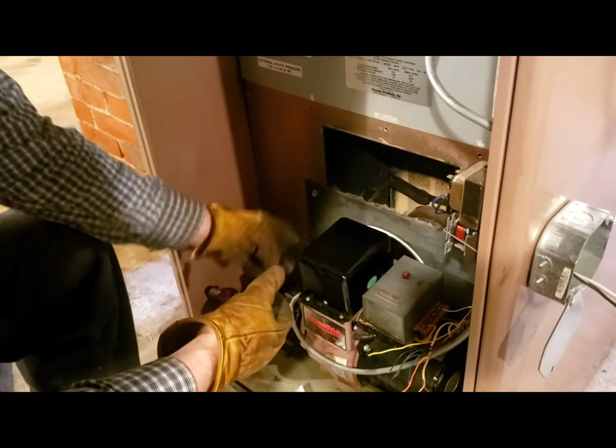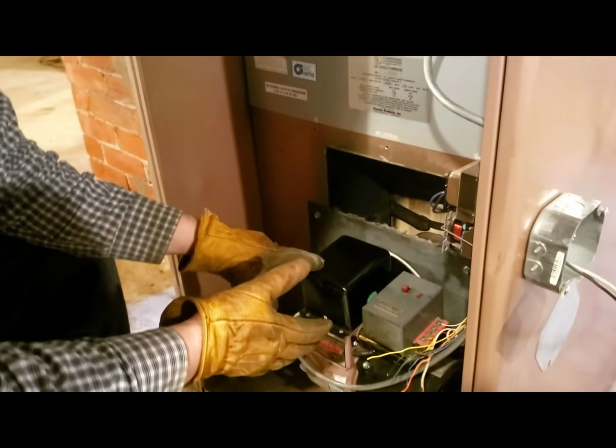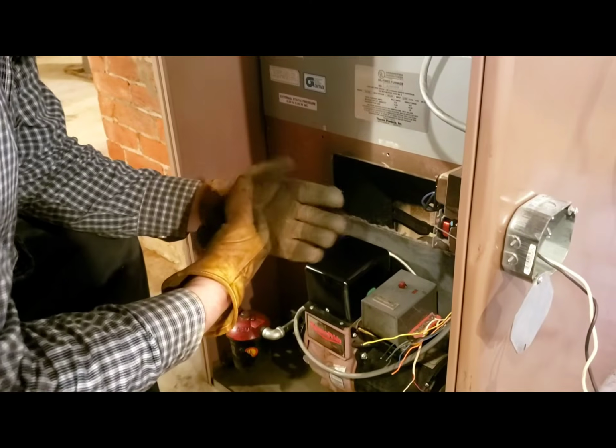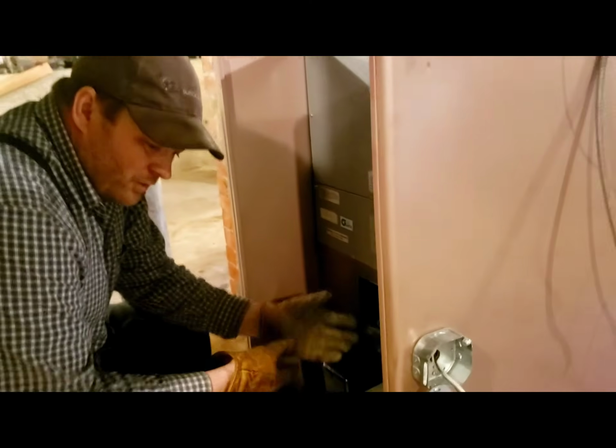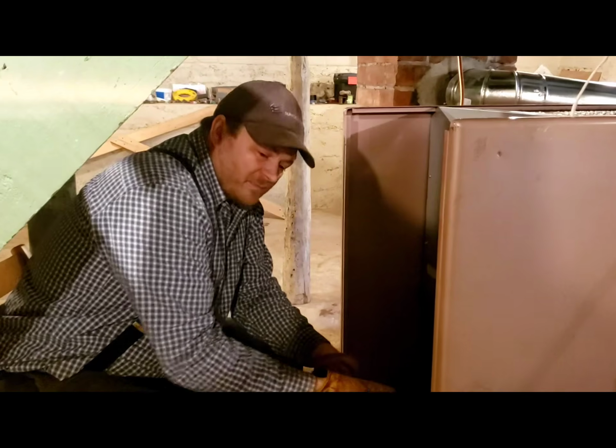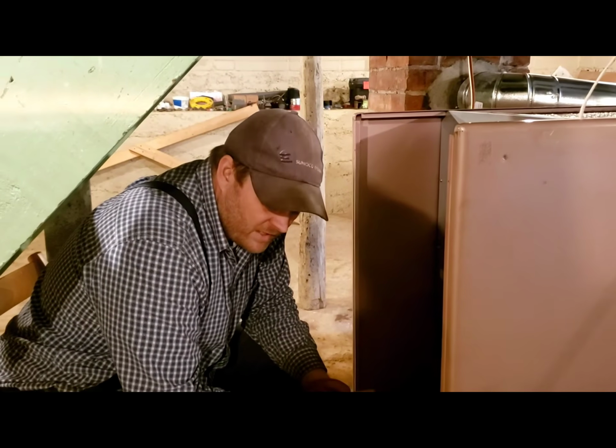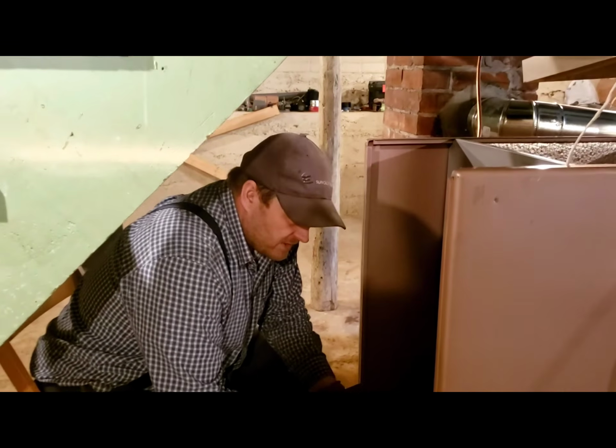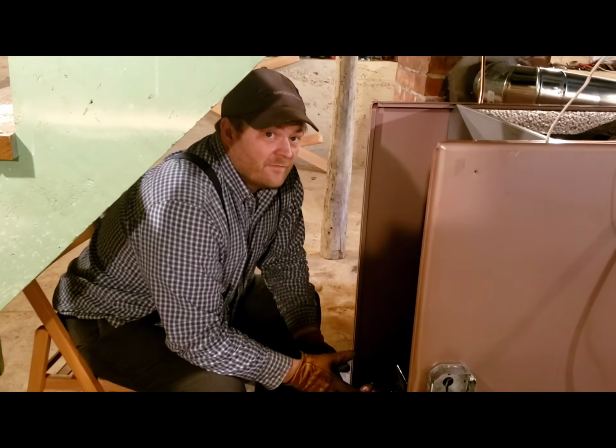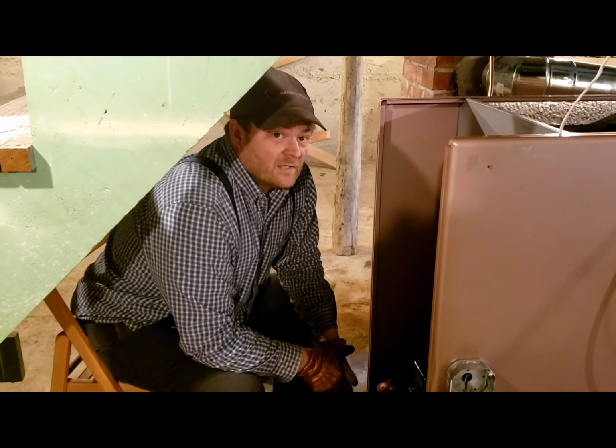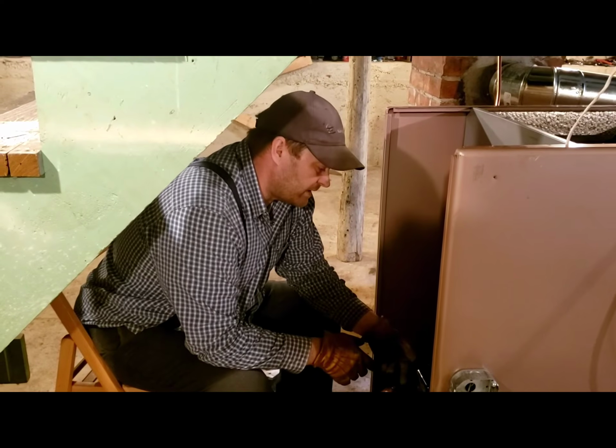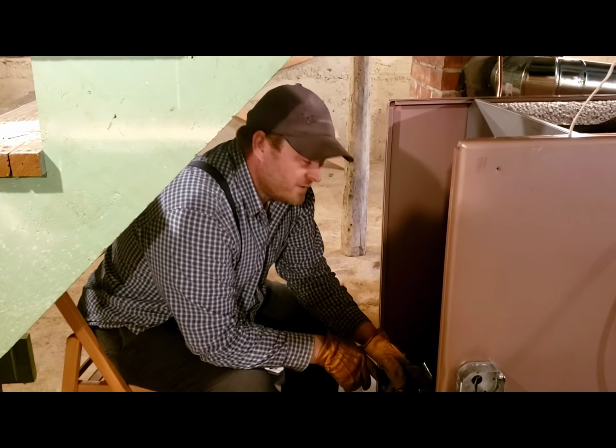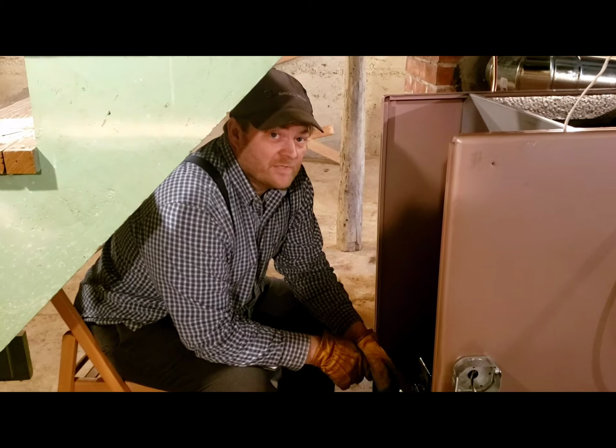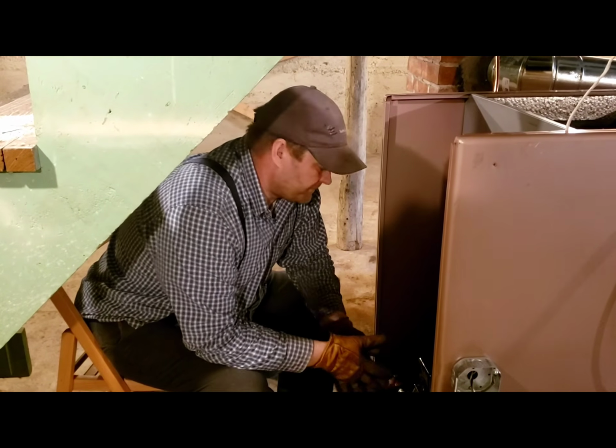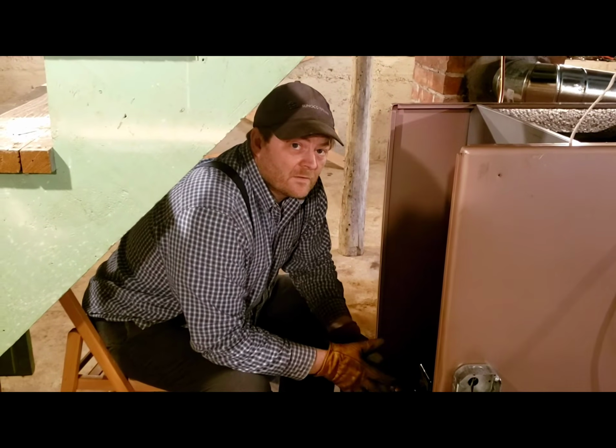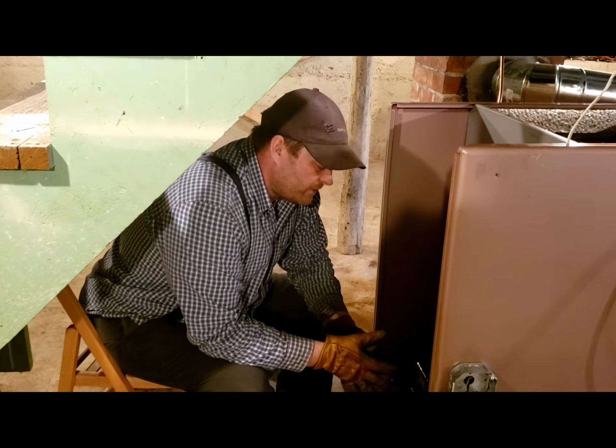The newer ones, they have a small transformer because they only run for a few seconds. And then the idea is the oil burning in the chamber lights the oil burning that's coming in behind it, and you don't need the spark. And that's true most of the time in okay conditions. But there's lots and lots of no heat calls and frozen houses in the winter because a storm blew the flame out. It locks you out on reset, and you have no heat. There's nothing there to restart it. So I don't like them. So when people say they're hitting reset over and over and nothing's happening, that wouldn't be how that worked.